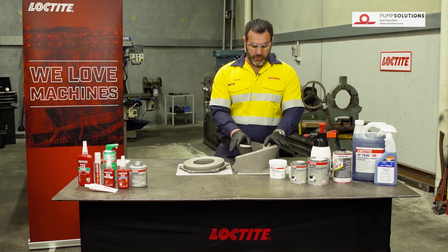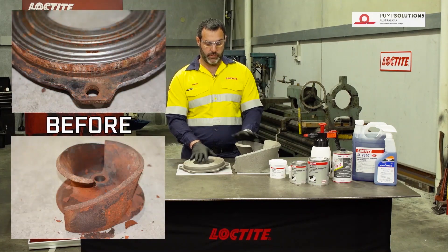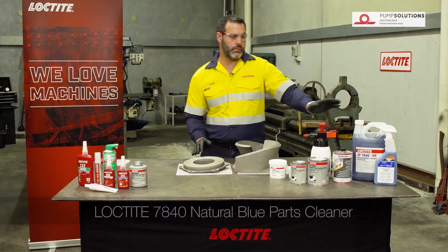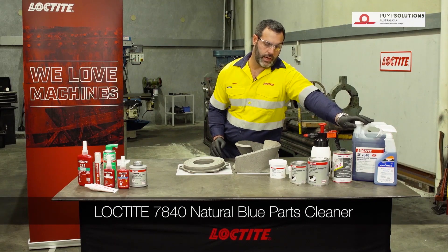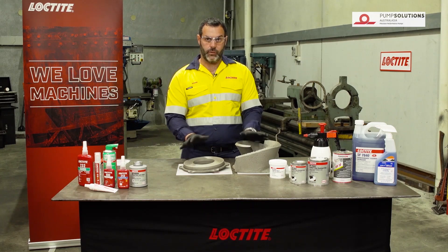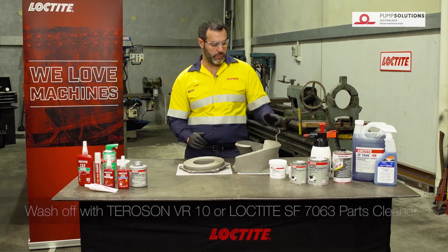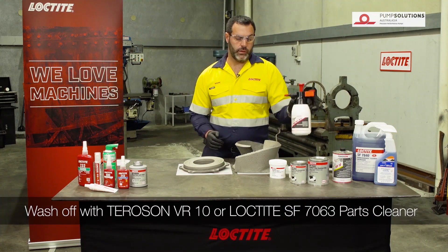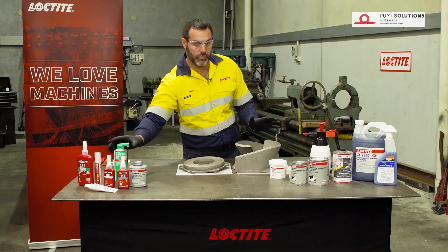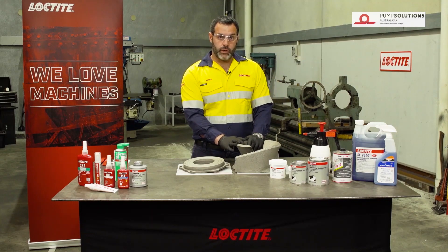With any type of repair work or coating work, the most important part is to make sure the surface is prepared well and cleaned. Prior to being grit blasted, these were cleaned using Loctite SF7840. Then they were grit blasted. After that we blow them down with nice clean dry air, and then finally we give them a quick wash down with a solvent — either VR10 or SF7063. Both of these products can be used as a solvent cleaner.